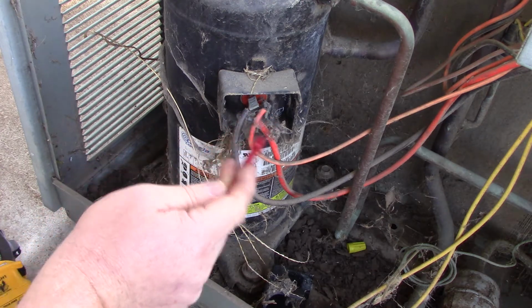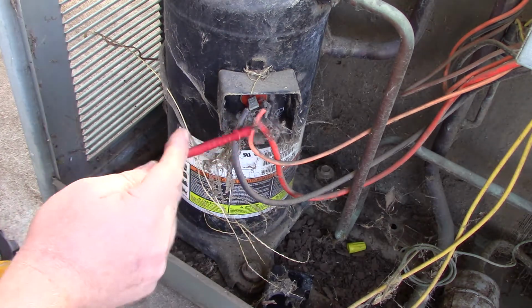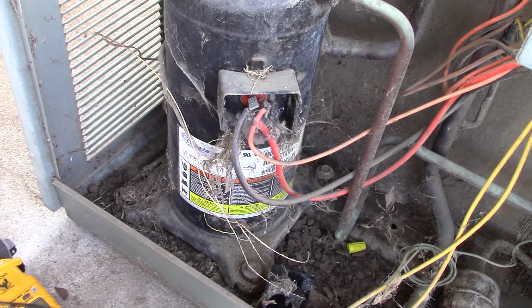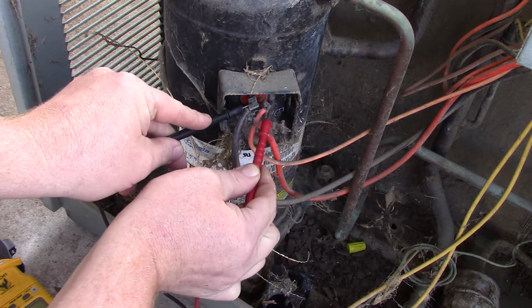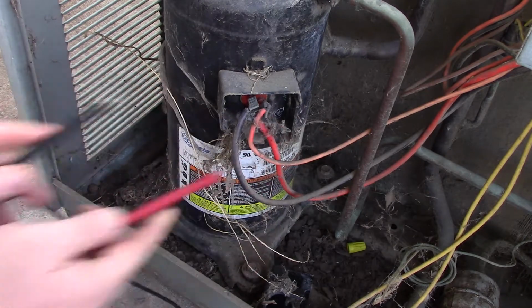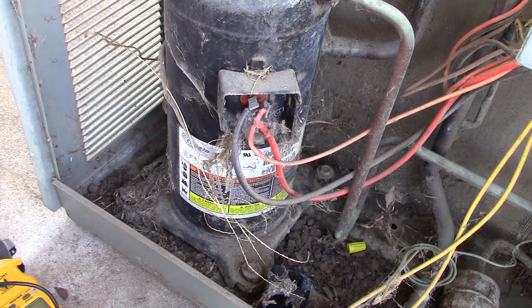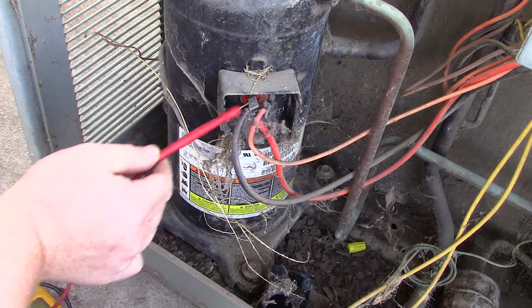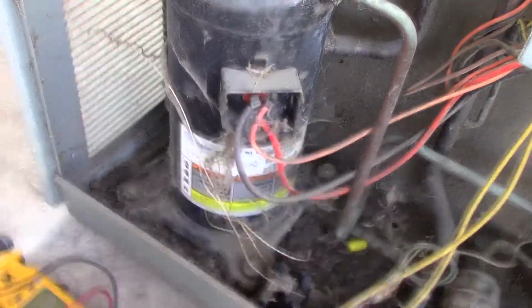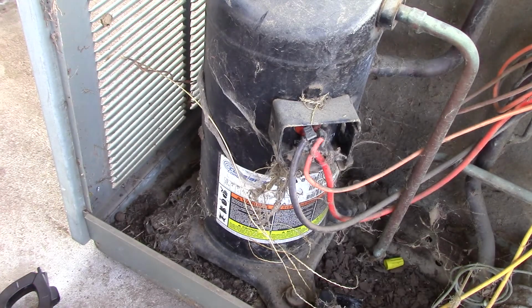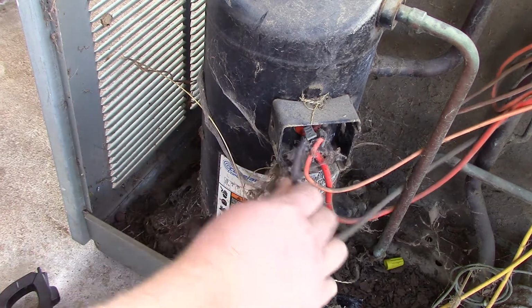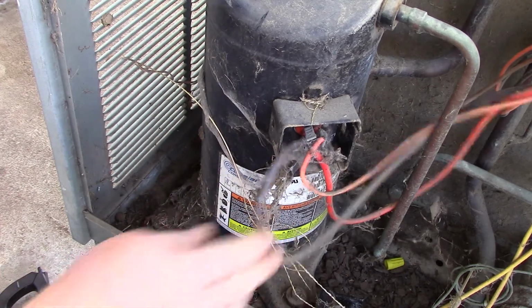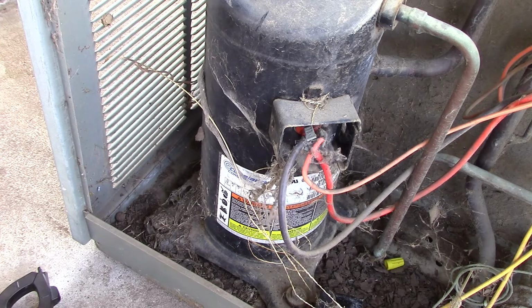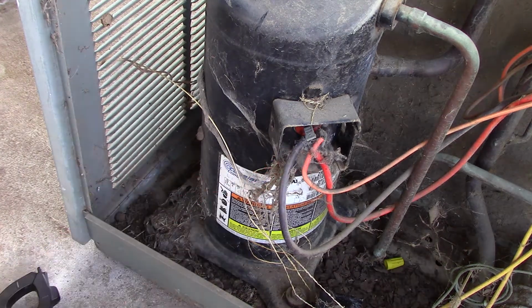You have to disconnect all your wires here, because those wires are connected up to that contactor, which includes the condenser fan motor. If I have a reading here on ohms but the compressor is not running, it's got to be good? No, this could have an OL on it, whereas it's going to go back through the contactor in that junction box, because you see how it's all connected there, or you saw from the previous video, to the condenser fan. All you want to do, let's see, there's a big old spider on there. I don't want to get my hands on it. I don't like spiders. But you just go from terminal to terminal.